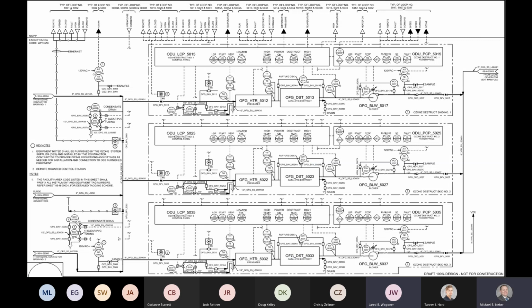To walk you through what we're seeing here: inside the dashed boxes is a skid that's being provided. Sundt will procure that ozone destruct skid from the manufacturer. Everything inside that box area, piping, valves, instrumentation, is provided by the skid, set by the mechanical contractor, and electrical will tie in those contacts and SCADA points.